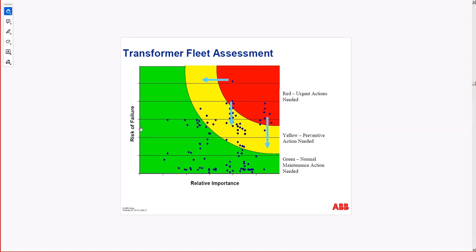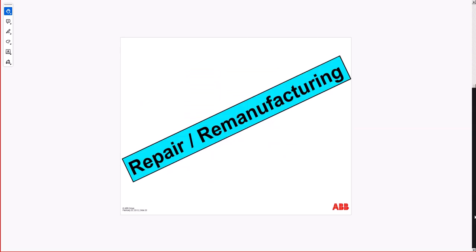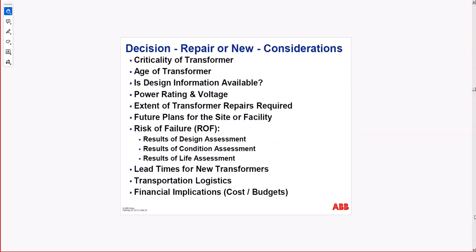This is just an example. Risk of failure: you see red, yellow, green. We classify our system the same way. I think we also have white in the color scheme of the system. Red is urgent, yellow is preventative, and green is normal operation. Repair or remanufacturing: the decision, repair or new, is based on the age, design, availability, power rating, voltage, extent of transformer repairs, future plans, risk of failure from the failure criteria that we discussed, and then lead time for new transformers.